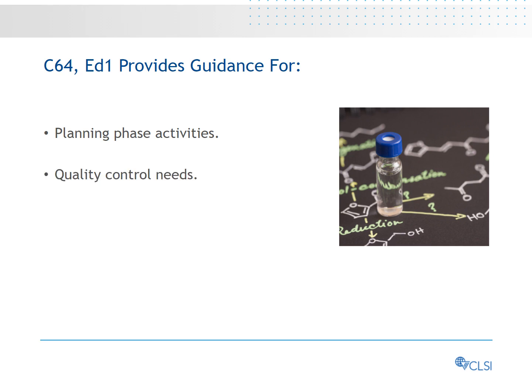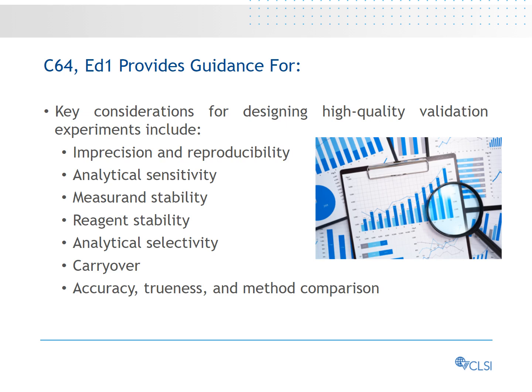QC samples are essential for monitoring test performance characteristics during development and for routine analysis of patient samples after the test has been validated. After developing an initial version of the method, the test developer should perform a preliminary evaluation of test performance. The key considerations for designing high-quality validation experiments include imprecision and reproducibility. The goal of evaluating imprecision during validation is to assess error arising from run, day, reagent lot, instrument, and operator differences. Reproducibility experiments expand error assessment to between-site and between-laboratory studies. Analytical sensitivity: the lower limit of the measuring interval can be defined as the minimum analyte concentration that results in measurements with adequate accuracy and imprecision for the test's clinical purpose.